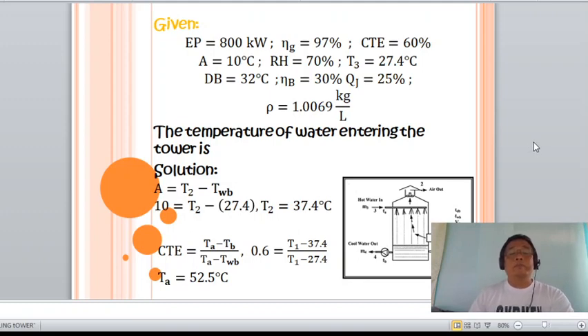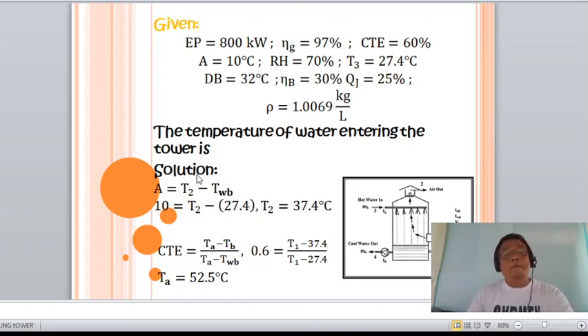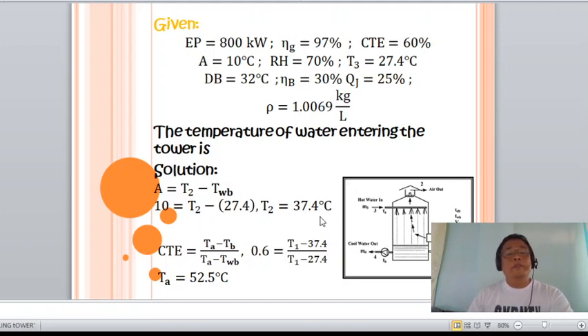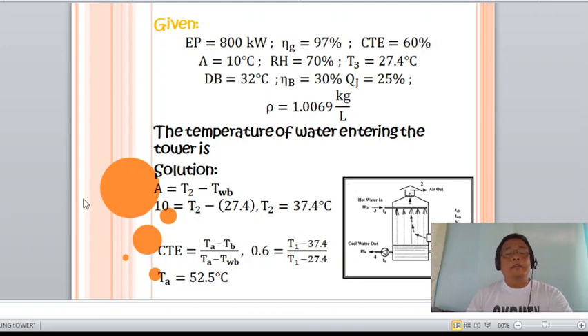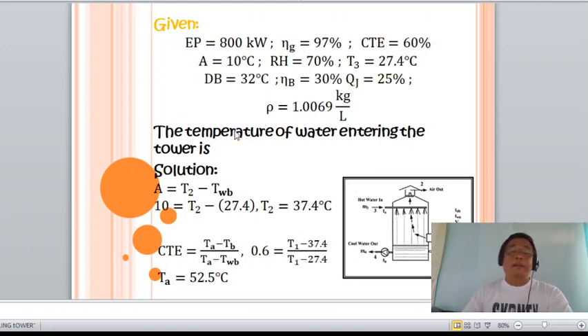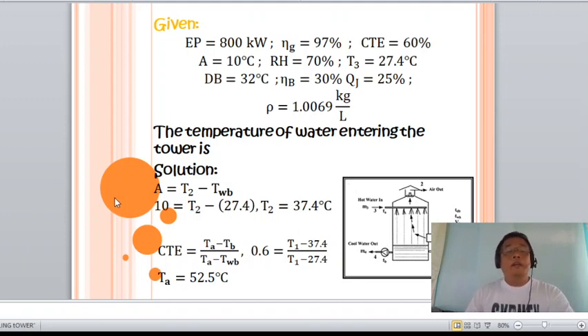Knowing that the approach equals T₂ minus the wet bulb temperature, where T₂ is the temperature of the leaving cold water, we get T₂ = 37.4°C. Substituting the cooling tower efficiency of 60 percent and solving for T₁ — the temperature of water entering the tower, which is the hot water coming from the diesel engine — the temperature of water entering the tower is 52.5 degrees Celsius.